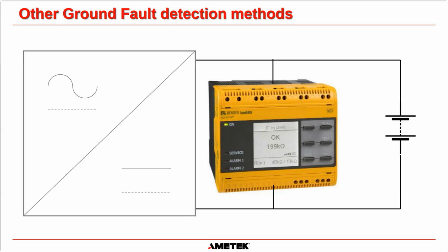So if you have a Bender system or something similar to how a Bender DC ground fault detection operates, you will not get the halfway voltage between positive and ground and negative and ground. The Bender actually gives you some really weird readings between positive and ground and negative and ground. And it's a proprietary circuit that they use. I have no idea how it works, but just know if you have a Bender system on your DC system and it is your form of ground fault detection, then you are not going to measure the halfway point between positive and ground and negative and ground. Okay.